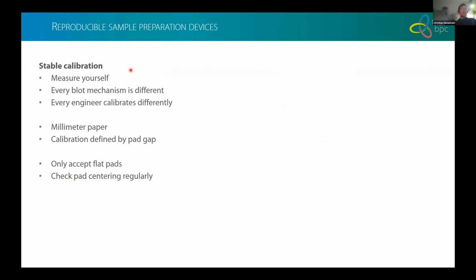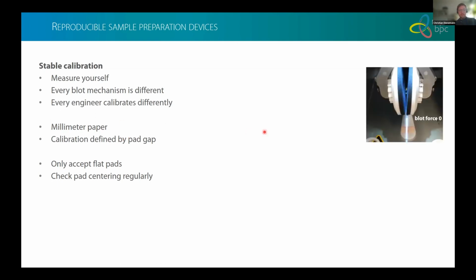Even between machines and between the engineers that calibrated the machines, there will be differences. So we set out to always measure it ourselves. We started working with piezo elements to actually measure the pressure, but this didn't work out. It was too complicated and not very reproducible. So we stuck a piece of millimeter paper onto this white lid. It's an extremely simple solution.